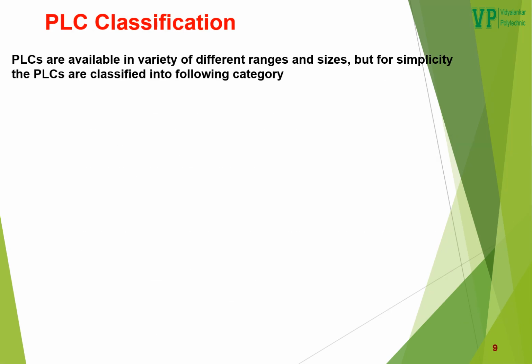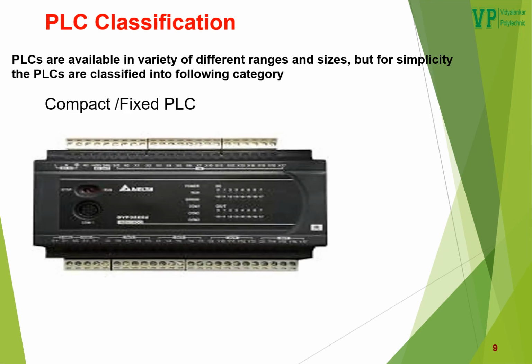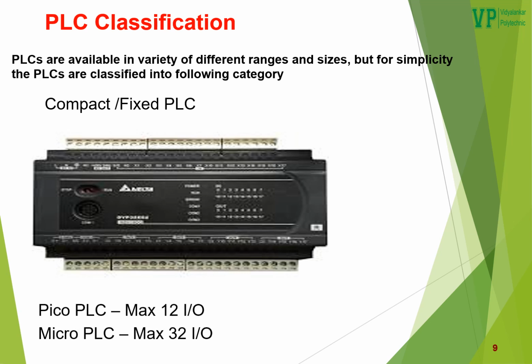PLC classification. PLCs are available in a variety of different ranges and sizes. But for simplicity, the PLCs are classified into two categories. They are fixed or compact PLC, and modular PLC. Under fixed or compact PLC, there are two types, Pico PLC and Micro PLC. Pico PLC has 12 input-output points and Micro PLC has 32 input-output points. Other than this, compact PLC basically means it is one unit which has an integrated processor, power supply, memory, input module, and output module. Everything is integrated in one unit.